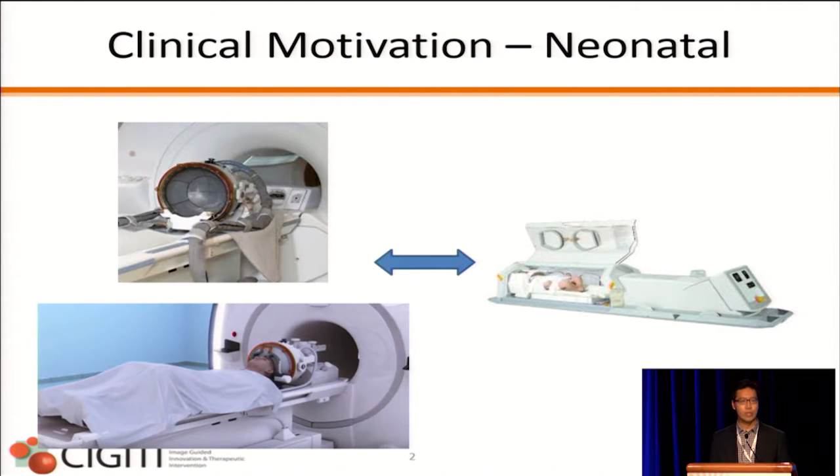As we've seen in earlier presentations, transcranial MR-guided focused ultrasound is available and developed by InSightec, and it's used in various trials for essential tremor. One of the problems is that transcranial systems are quite large, and they require fixation screws applied to the patient, who is then placed into a silicone cooling bag. In contrast, the picture on the right shows a neonatal MRI incubator used for scanning, with a neural imaging coil and the baby sitting inside. Our project was to investigate whether we can develop a transcranial system given the constraints of the incubator and the MRI bore space itself.